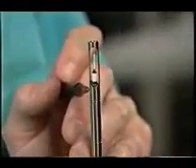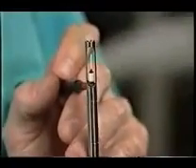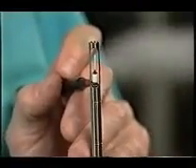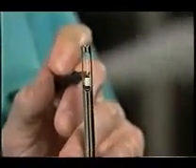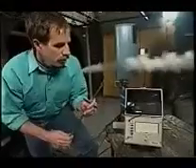Now, these are very sensitive devices. I have another one here hooked up to this meter, and you can see that just my breath can cause it to go to full-scale deflection. So we can take the probe and actually put it into the airflow, which is running fairly slowly here, and you can see that I get a fairly accurate measurement. And you can see that it responds fairly quickly when I take it out of the flow.